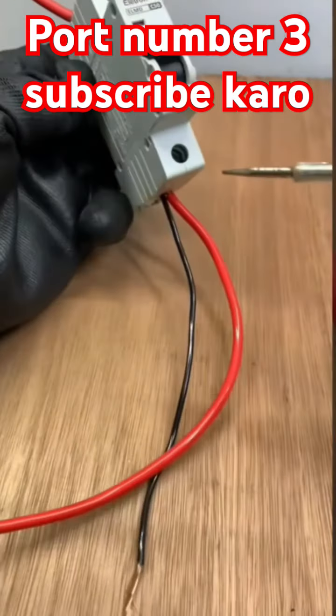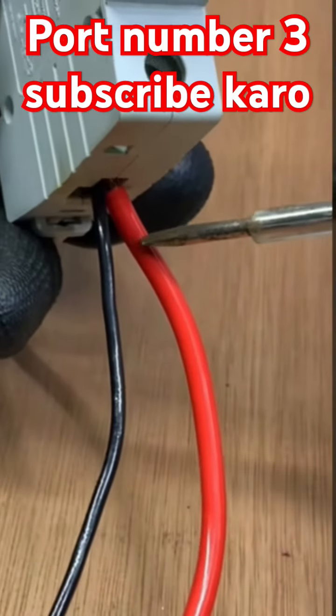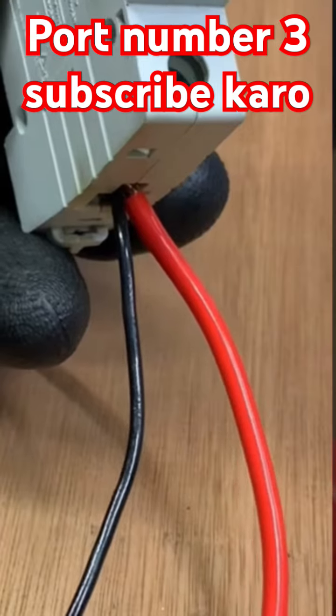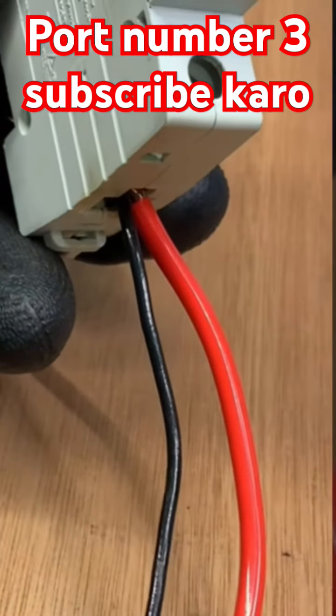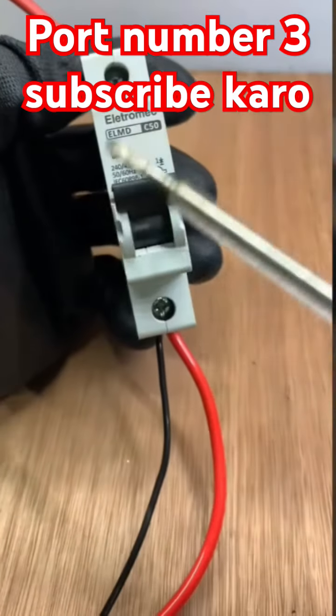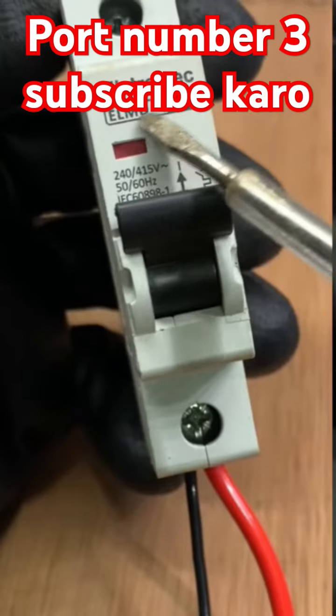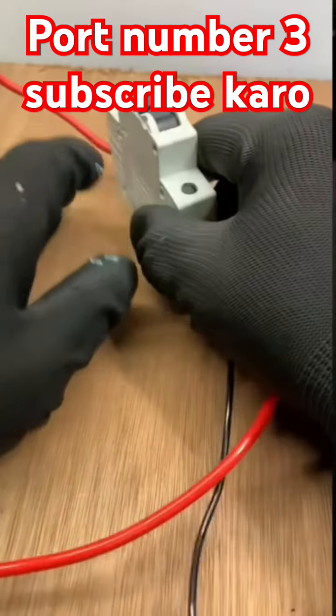Look here, at the output I'm connecting a 6mm red cable and a 1.5mm cable to the same circuit breaker output, because there's no space in the panel. So you go there and use a circuit breaker that's already in the installation. But this circuit breaker is 50 amps.